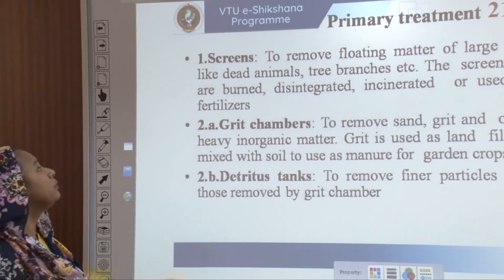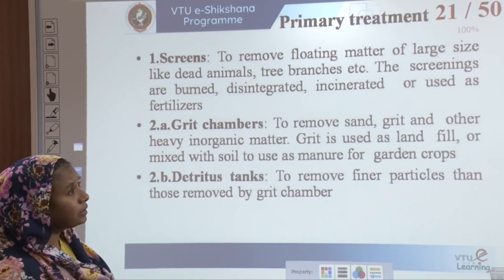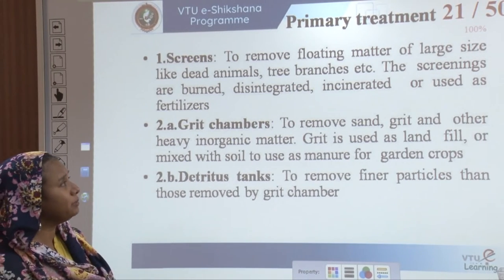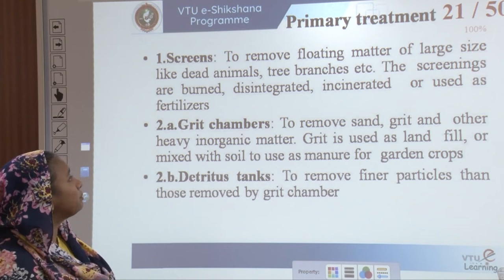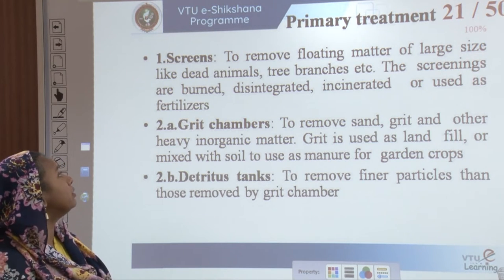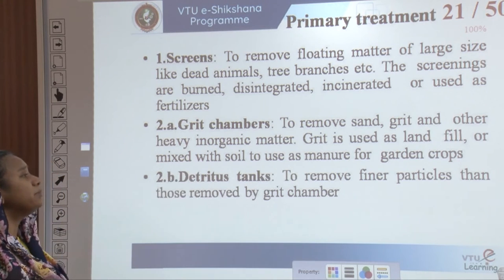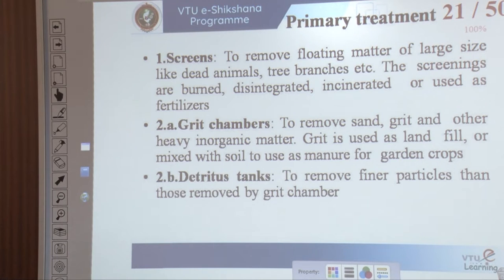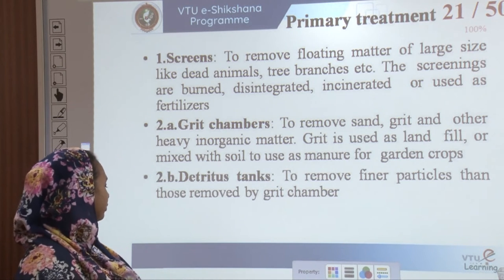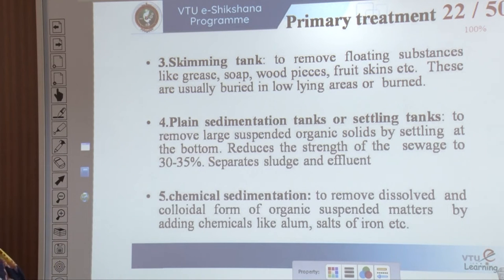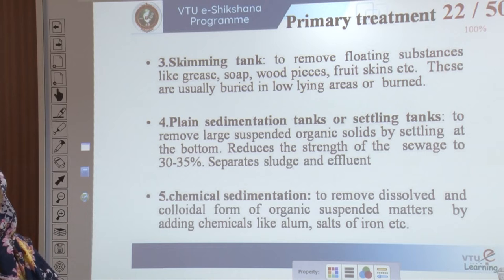In primary treatment, screens are used to remove all floating matter of large sizes like dead animals, tree branches, and plastic waste. The screenings are burnt, disintegrated, incinerated, or used as fertilizers. Grit chambers remove sand, grit, and heavy inorganic matter; this grit is used as landfill or mixed with soil as manure for garden crops. A detritus tank removes finer particles than those removed by grit chambers. Then we skim all floating substances like grease, soap, wood pieces, and fruit skins, which are usually buried in low-lying areas or burnt.